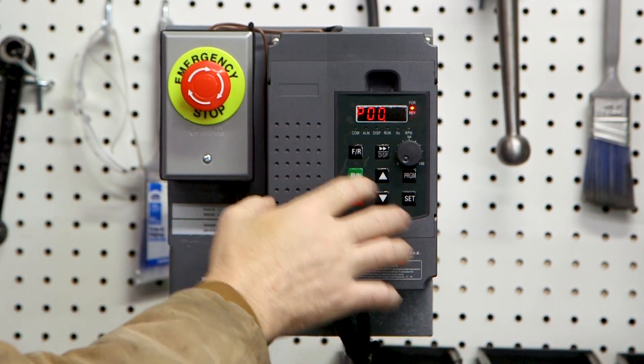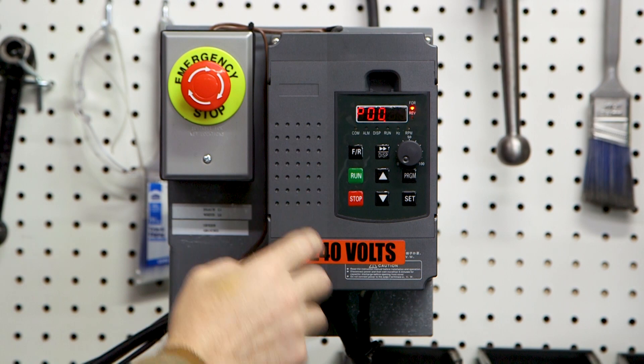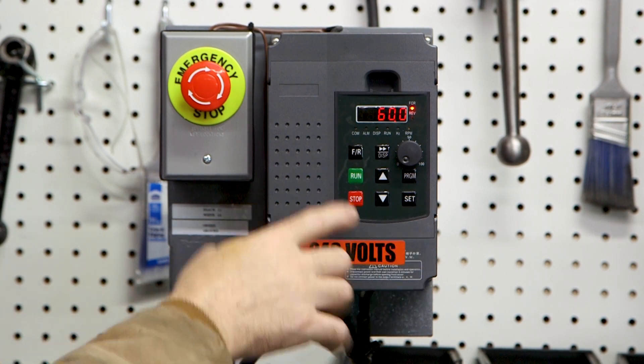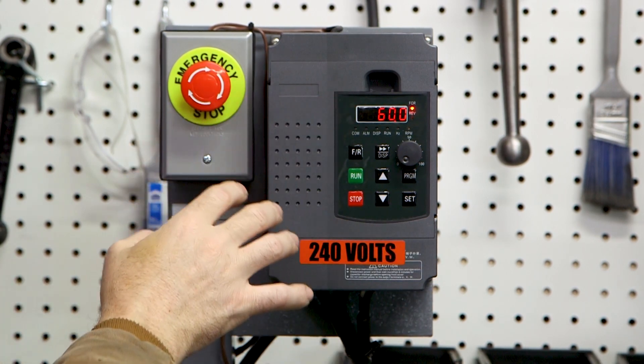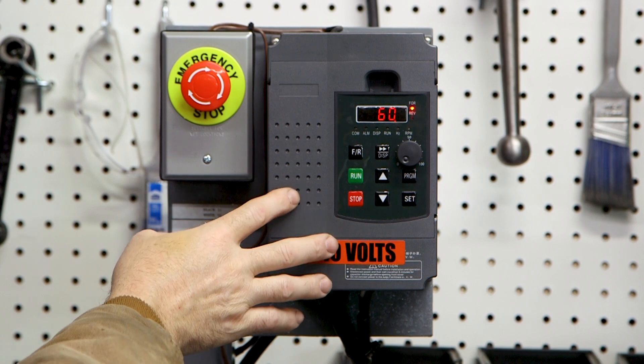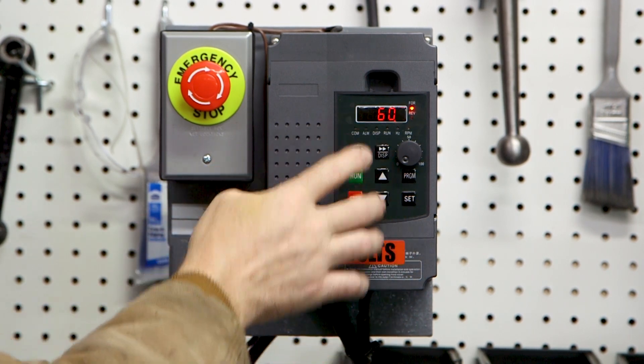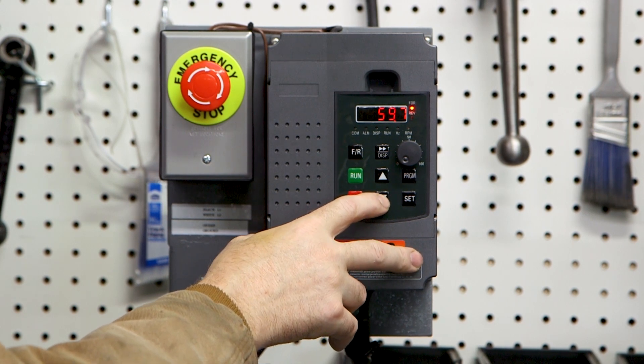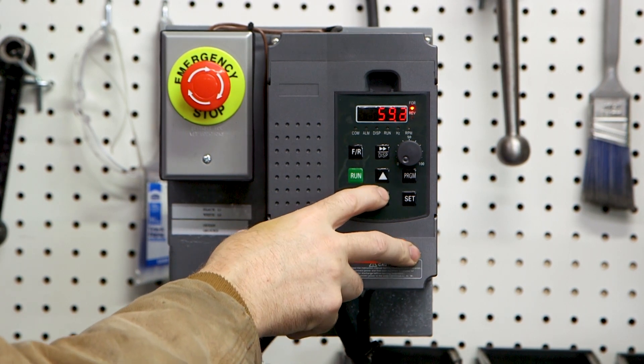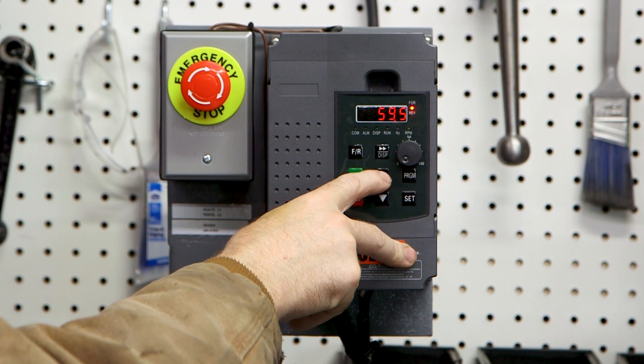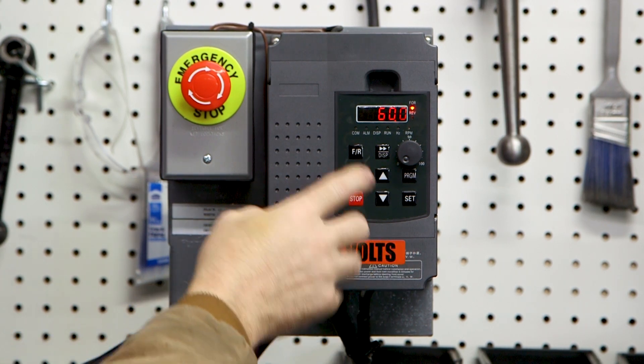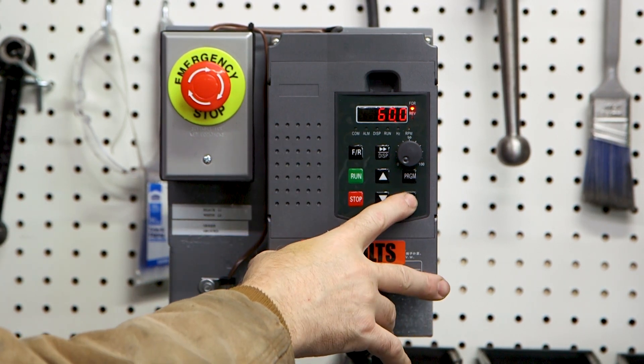So to set this, you've got your P code flashing and you hit set. And mine is set to 60 because I already changed it. If you just turn this VFD on right out of the box, this will be set at 50. To change that, you use the arrow buttons and you set this to what you need. So in the US, we have 60 hertz power. So that's what I set it to. And then to get it to take, you hit set.